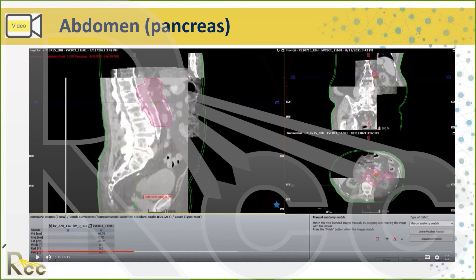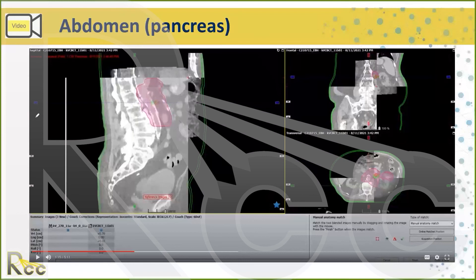The manufacturers of these machines have really refined the reconstruction algorithms, so the matching is pretty seamless. There are some inherent inaccuracies — we're talking about geometry with radiation therapy, so it's always a question of how accurate things are. The mechanical accuracy of the machine rotating around the isocenter is about two millimeters, so there are all these different accuracy considerations. Good question for your physicist.